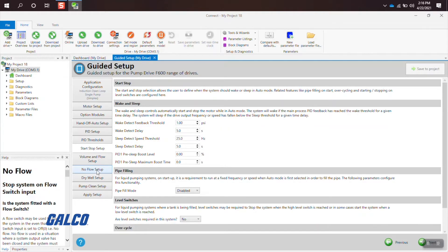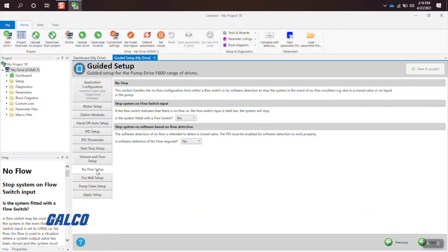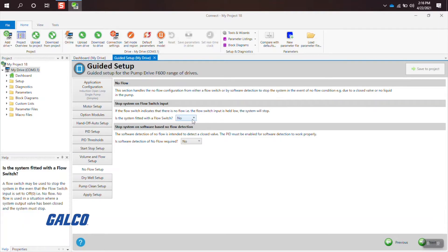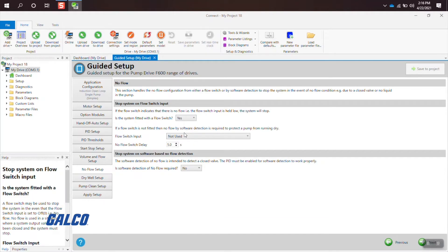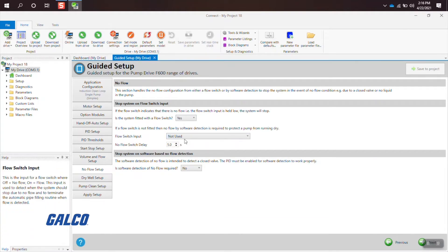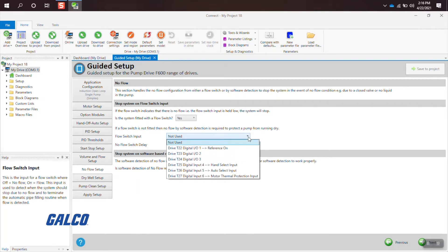Continuing down the application configuration tabs, you will then handle your no-flow setup, where you will select if the system is fitted with a flow switch. And if it is, you can then select the flow switch reference you want to use and the delay time.